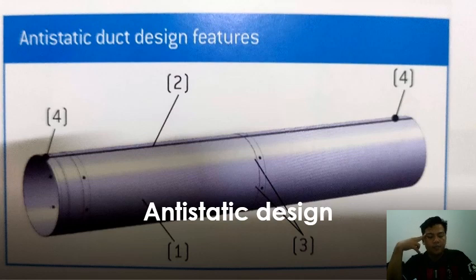Anti-static design is intended for rooms where a build-up or uncontrolled discharge of static electricity must be avoided. The anti-static system consists of four measures. Number one is a conductive fabric. Number two is a highly conductive strip installed all along the line of the duct. Number three is that all zippers are equipped with metal joints. Number four is a grounding point at the end of the duct.